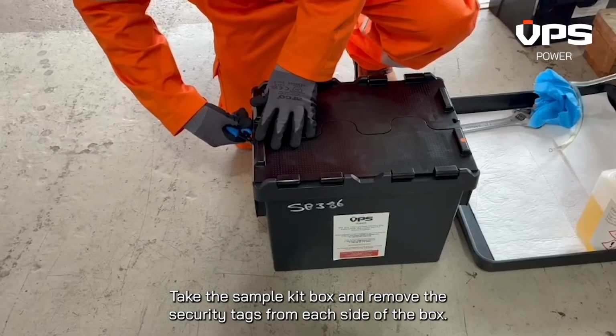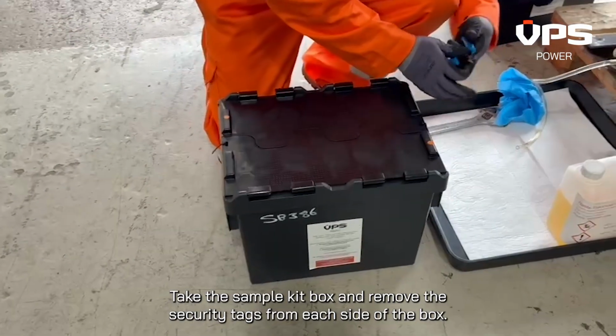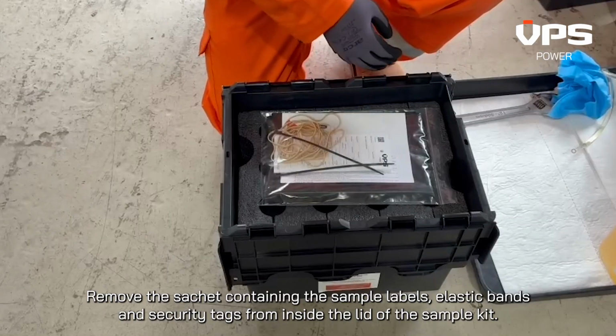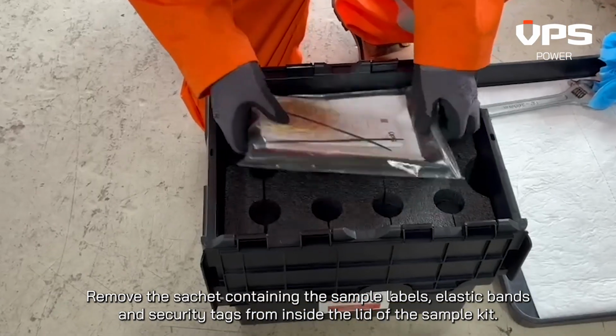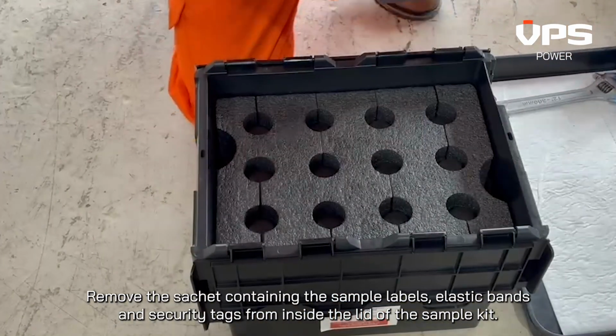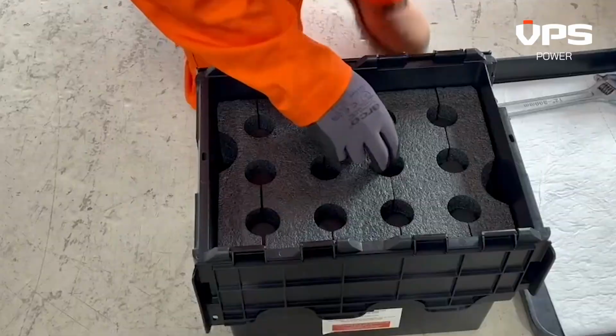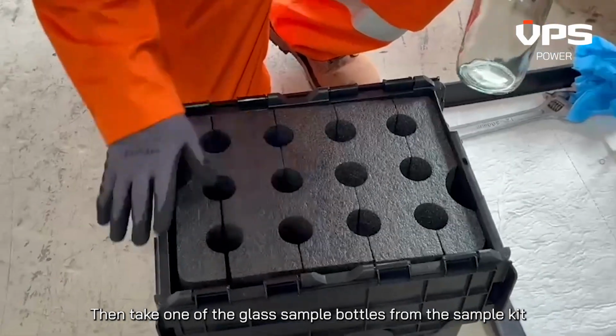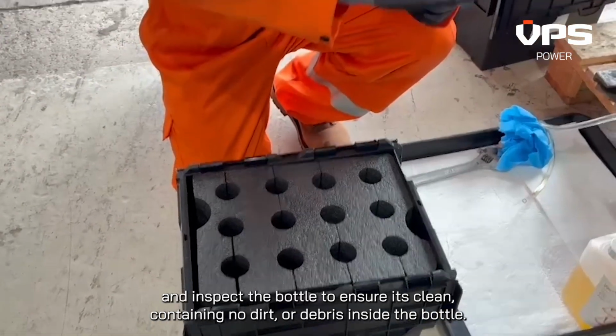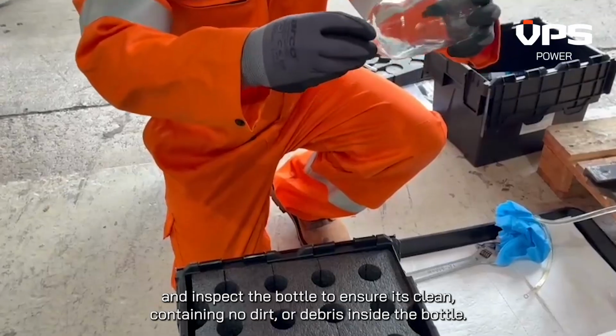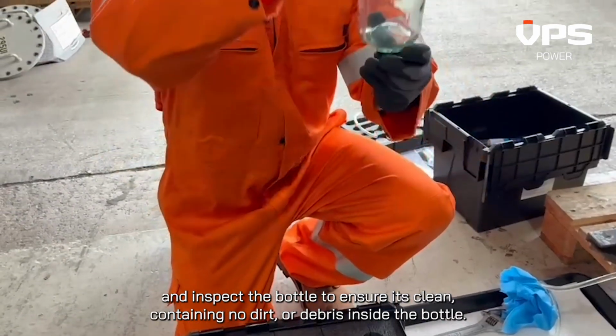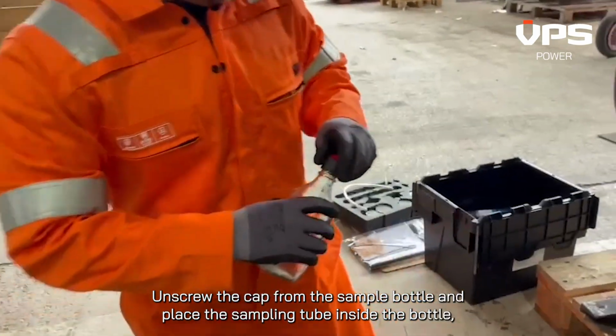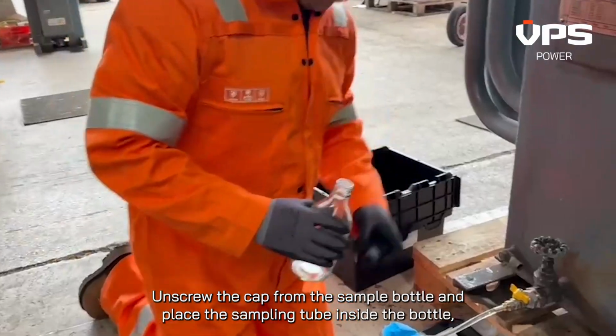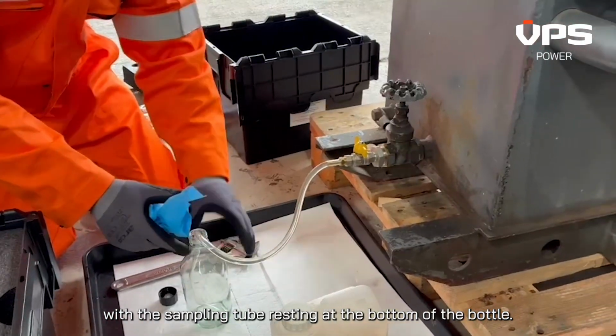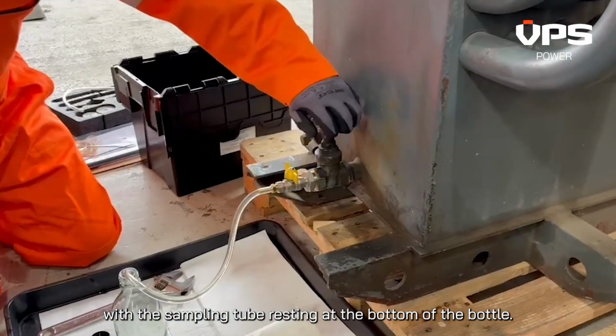Take the sample kit box and remove the security tags from each side of the box. Remove the sachet containing the sample labels, elastic bands and security tags from inside the lid of the sample kit. Then take one of the glass sample bottles from the sample kit and inspect the bottle to ensure it's clean, containing no dirt or debris inside the bottle. Unscrew the cap from the sample bottle and place the sampling tube inside the bottle with the sampling tube resting at the bottom of the bottle.